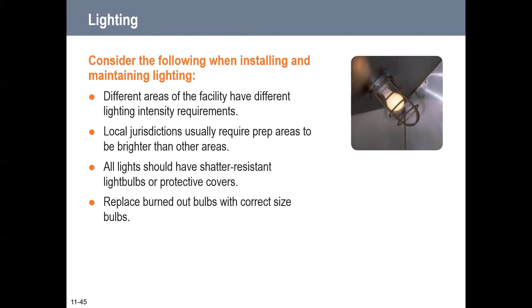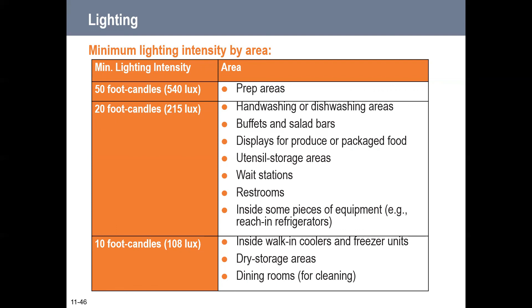Minimum lighting intensities by area are measured in foot candles or lux. Prep areas need 50 foot candles, or 540 lux, which is your highest lighting intensity. Dishwashing areas, buffets or salad bars, displays, utensil storage, wait stations, restrooms, and inside some equipment like refrigerators need 20 foot candles, or 215 lux, since they don't have to be as bright as prep and cook areas. Inside walk-in coolers and freezer units, dry storage, and the dining room for cleaning purposes all need 10 foot candles, or 108 lux.